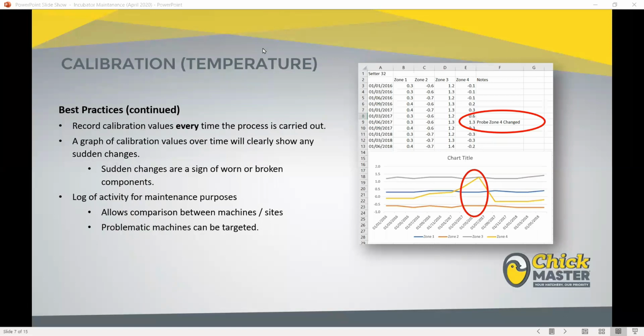Logging these values also allows you to make comparisons directly between individual probes within a machine and also between machines on an individual site. So if you have 12 incubators on your site and all of them without question calibrate to around 0.6 of a degree or below, but you have one incubator that requires a 1.2 offset, you know something's not quite right with that last incubator. And it allows you to justify any hardware replacements far easier.